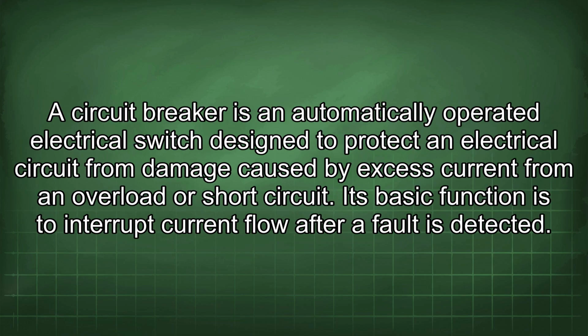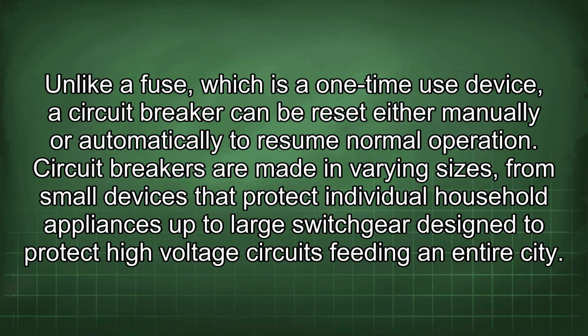A circuit breaker is an automatically operated electrical switch designed to protect an electrical circuit from damage caused by excess current from an overload or short circuit. Its basic function is to interrupt current flow after a fault is detected. Unlike a fuse, which is a one-time use device, a circuit breaker can be reset either manually or automatically to resume normal operation. Circuit breakers are made in varying sizes, from small devices that protect individual household appliances up to large switchgear designed to protect high-voltage circuits feeding an entire city.